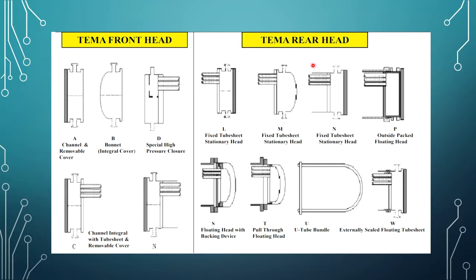According to TEMA standards, the main types of front head are: A type (removable cover type), B type (bonnet type, also called integral cover type), and D type (used for special high pressure purposes), as well as C type and N type. The different types of rear head include L type, M type, and N type, which are fixed tube sheet rear heads, and P, S, T, U, and W types, which are floating type rear heads.